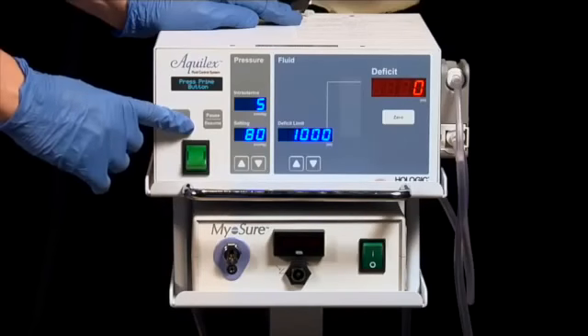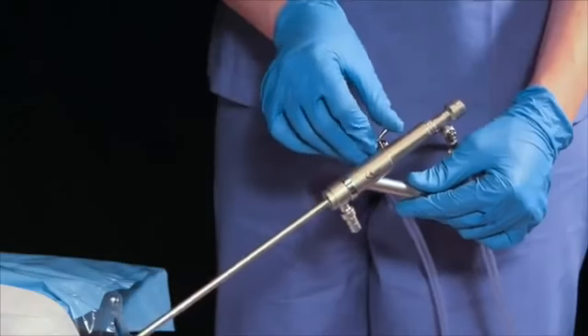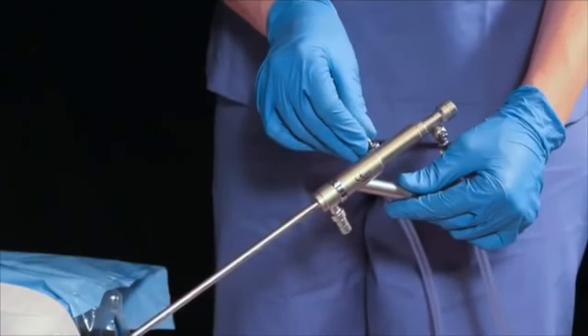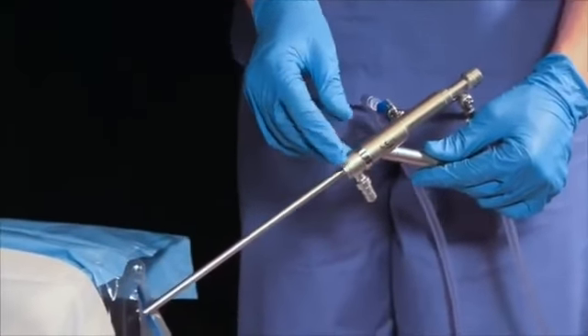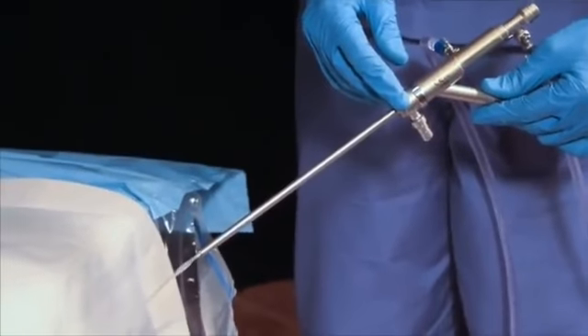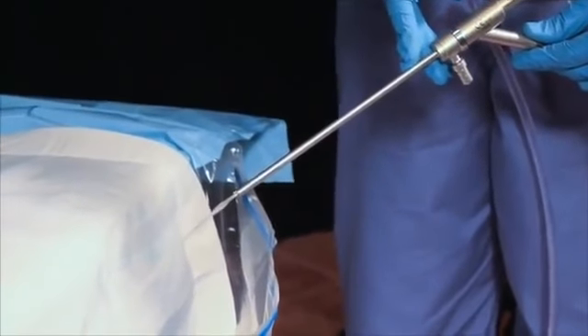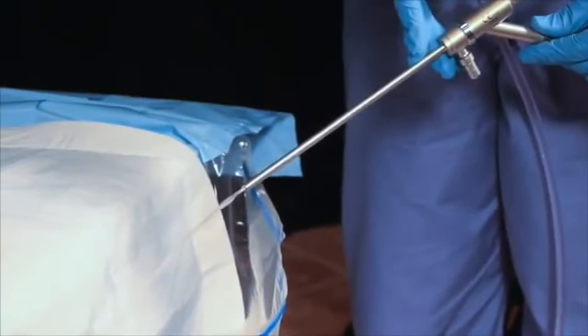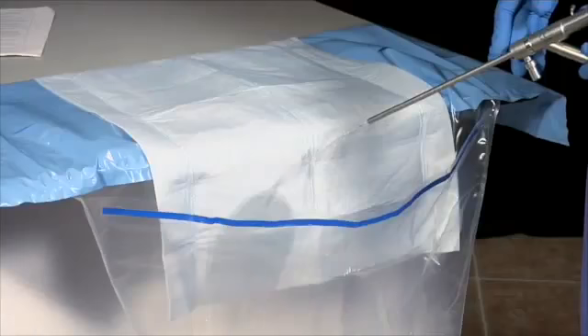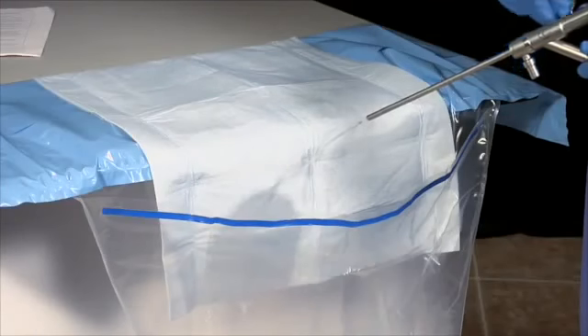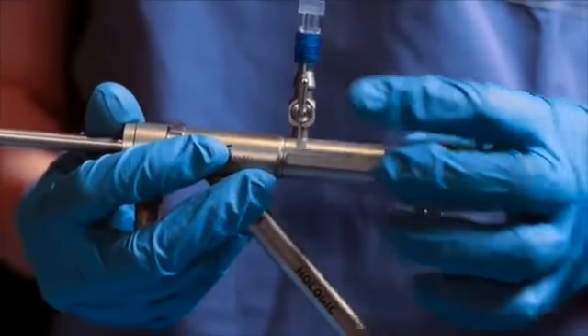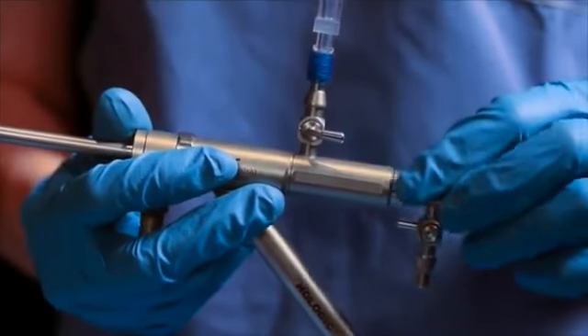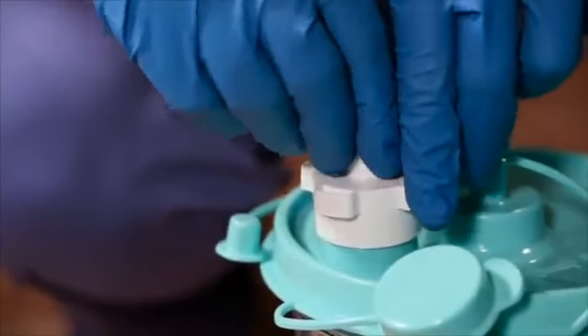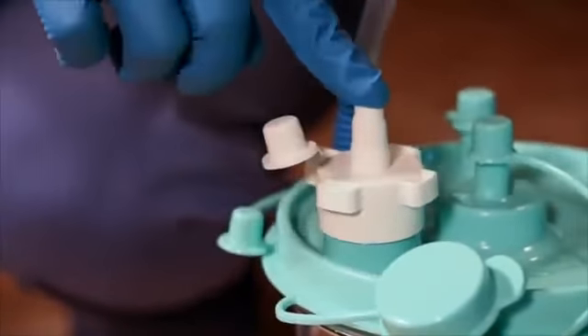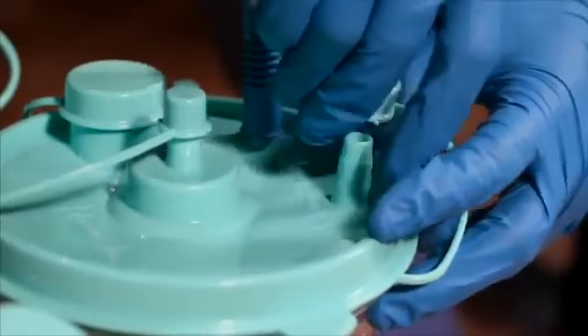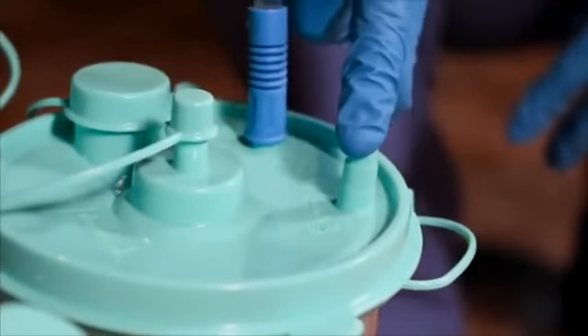Press the prime button. The prime mode will purge air from the tubing and complete the automatic lumen calibration, ensuring optimal inflow at all times during the procedure. Once prime is completed, you will hear a beep. Close the hysteroscope inflow stopcock. Test the vacuum level by placing a finger over the tissue trap opening and the patient port to ensure that the canisters are sealed.